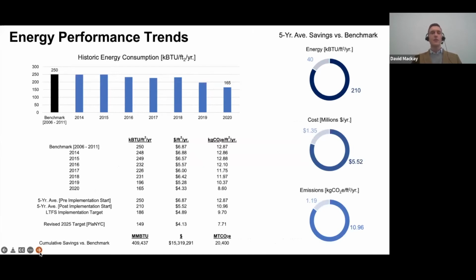With that calibrated energy simulation, we developed a benchmark evaluating five years, 2006 through 2011, with data shown in site energy use intensity, or kBtu per square foot per year. Our benchmark was 250 kBtu per square foot, and we've been trending downward steadily since, with 165 recorded in 2020. The fact that this building can turn down and achieve those reductions is a major achievement, because everything within it must be kept at very stringent indoor environmental conditions 24/7. So turndown, or being unoccupied in the traditional sense, doesn't really apply to the Met. We're very pleased to see these efforts showing up at the meter.